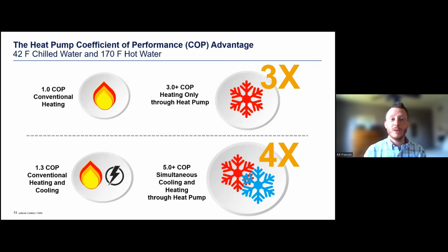Where things can get really exciting from an economic perspective is when large water-to-water heat pumps are applied, leveraging a chilled water load and a primary heat source. So basically, both cooling and heating at the same time. While operating in this configuration, COPs are over 5, and you can see from the image down below on the bottom half that it's about 4 times the amount of conventional cooling and heating from a COP perspective.